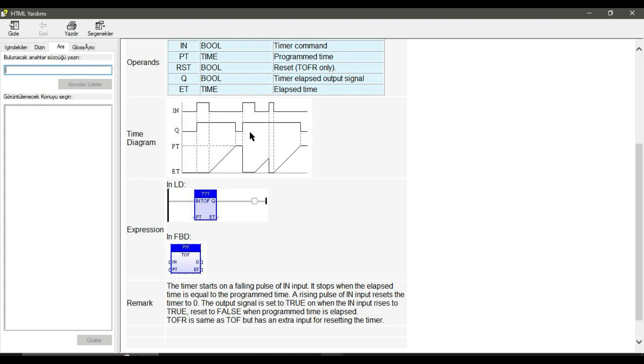This is why it is called an off delay timer. Note that if the elapsed time doesn't reach the preset time before the input turns on again, the output will not change, because as soon as the input turns on the elapsed time resets to 0.